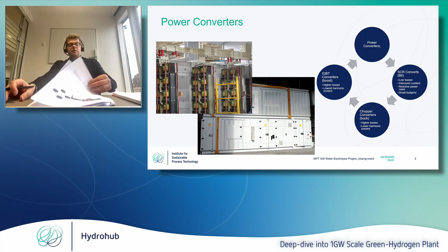On the user requirement side, coming back to the electrolyzer shown in the tables above and explained earlier: an electrolyzer consists of a number of modules stacked on each other. Depending on the size and number of modules stacked, you need to apply a certain voltage and current, both at start of life and end of life, to get the expected hydrogen output. The electrolyzer itself is quite flexible, and the power supply is also to some extent flexible.